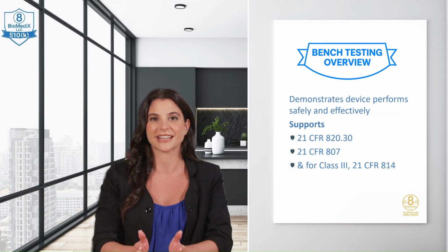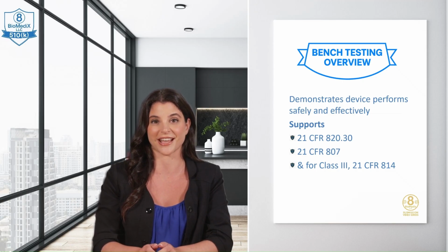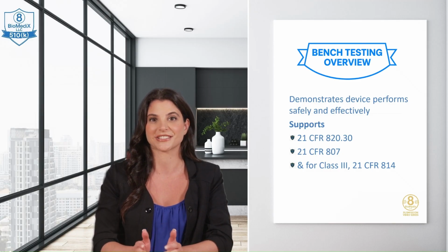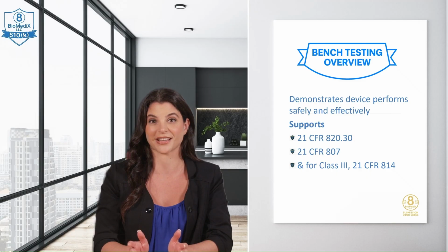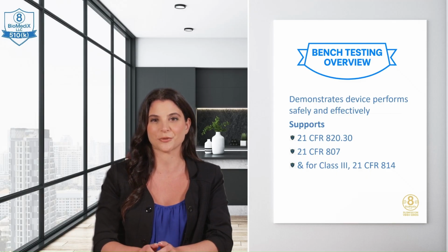Bench performance testing in eSTAR. Bench testing is your proof that the device performs safely and effectively. It's part of design verification under 21 CFR 820.30, 510K performance support under 21 CFR 807, and for Class 3 devices, design validation under 21 CFR 814. The FDA's guidance, Recommended Content and Format of Non-Clinical Bench Performance Testing Information, aligns closely with how eSTAR is structured.